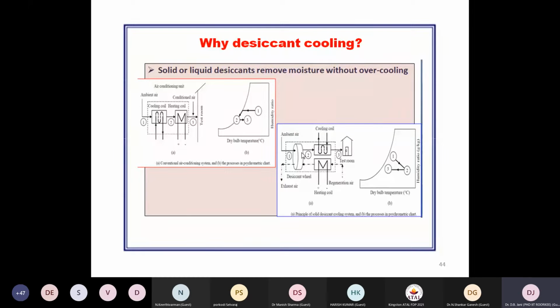After condensing out of the air onto the surface of the desiccant, we may find it saturated, just like our cloth being wetted. While removing water from tiles, we most of the time find our wetted rough cloth saturated, so we expose it to the atmosphere for further drying. Similar functions are required for a desiccant dehumidifier to carry out its drying operation, so that it can further perform dehumidification. We have to provide hot air to another section of the same wheel, called the reactivation section, and the air provided for the purpose is called the reactivation air, and the air being dried is called the process air.